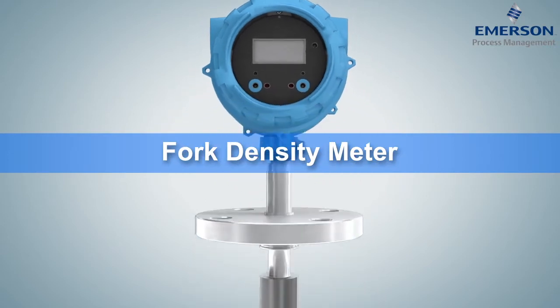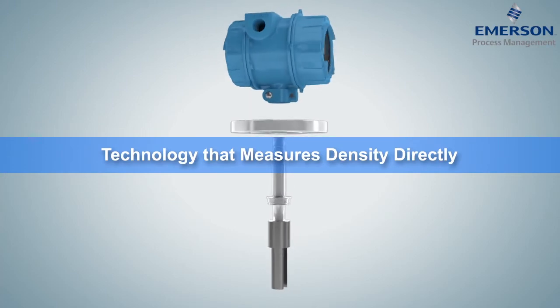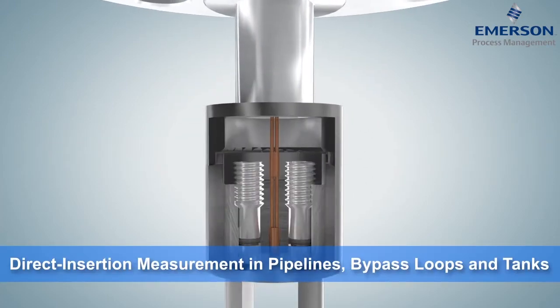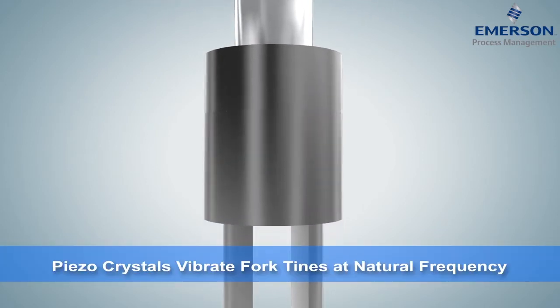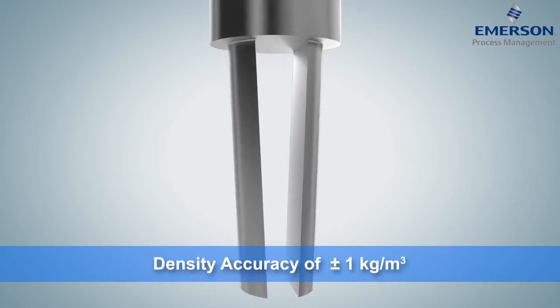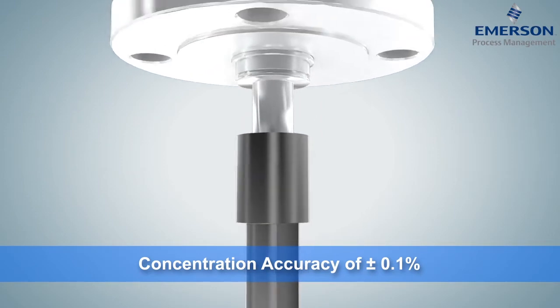Like a tuning fork defining the standard tone for an orchestra, the Micro Motion Fork Density Meter, or FDM, sets the standard for continuous, real-time direct insertion liquid density measurement in pipelines, bypass loops, and tanks. Piezoelectrically vibrated fork tines ensure accuracy within 1 kg per cubic meter for density and 0.1 percentage point for concentration.